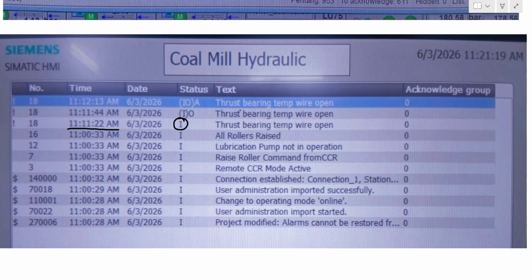After a few seconds, the alarm has vanished, the alarm has disappeared, and you can say that the fault has disappeared and it is now a normal scenario. So this is why after the incoming alarm, the letter O has been written, and O means outgoing alarm. The alarm has vanished. And the third row says that the alarm has been acknowledged by the operator. This is why A has been written. This is how the alarms can be interpreted in the PLC, HMI and SCADA.